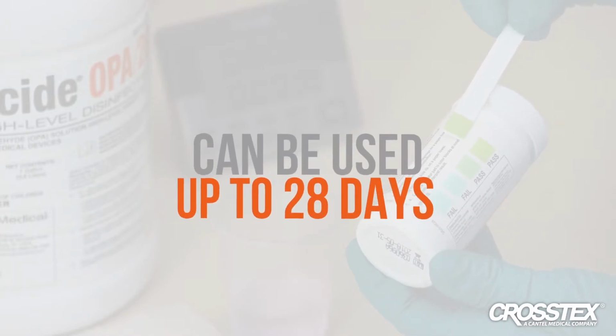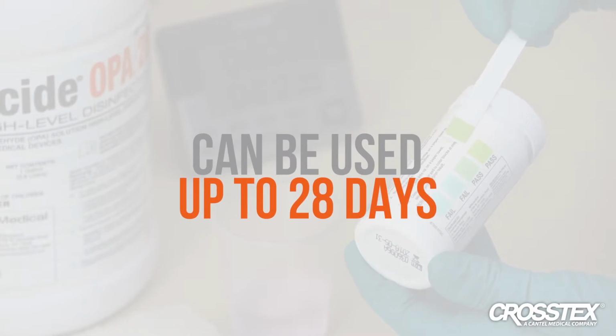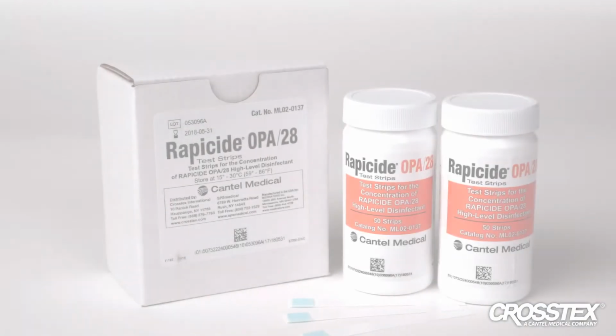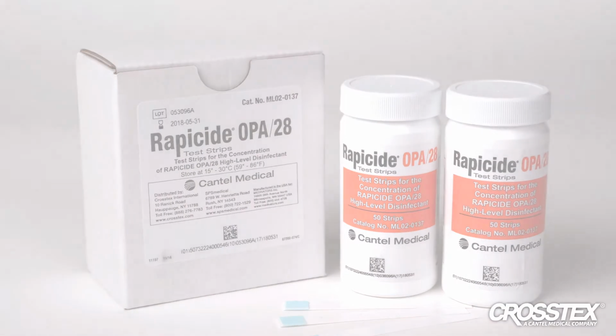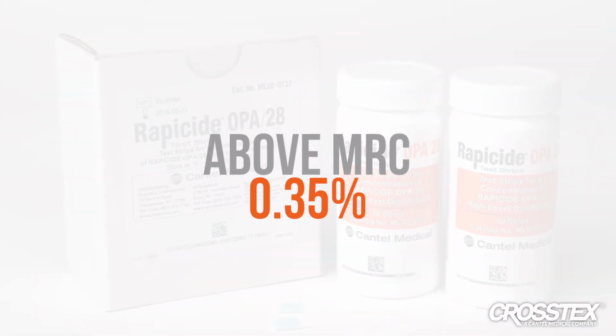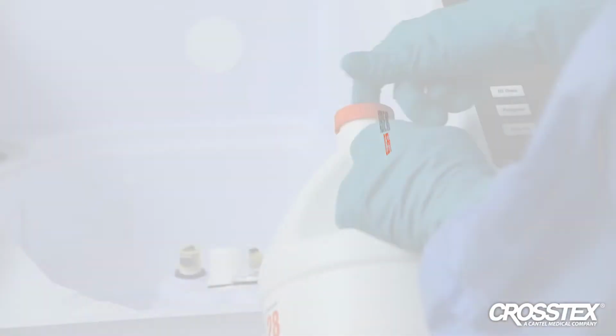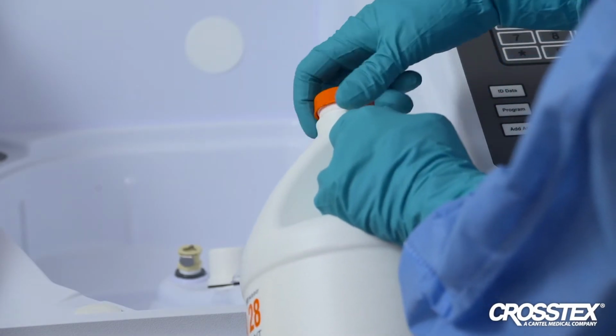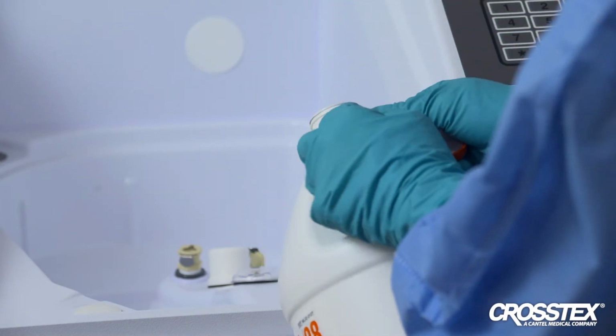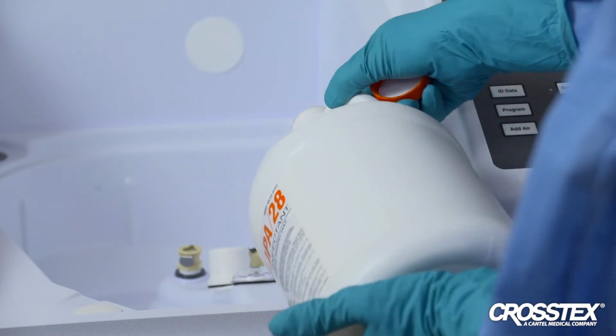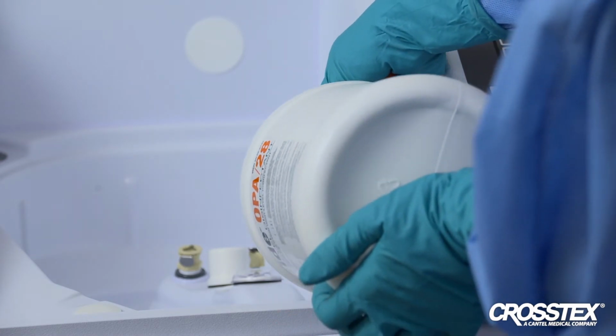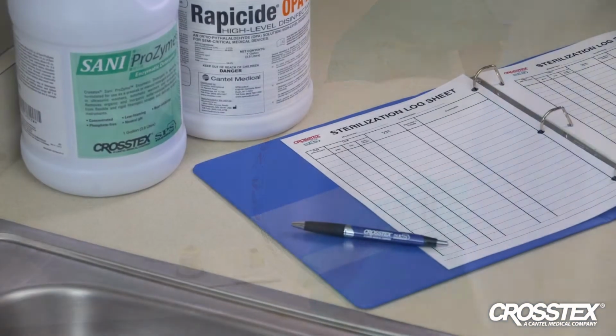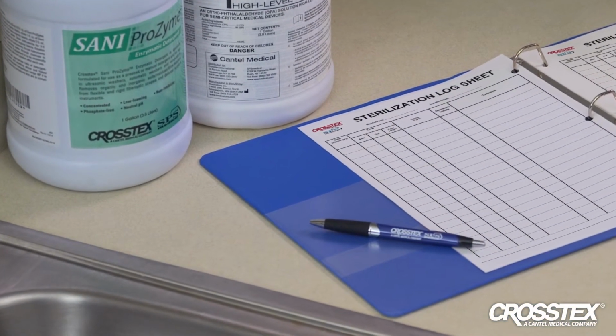The Rapicide OPA 28 HLD solution can be used for a period up to 28 days, provided that prior to each use, the concentration of OPA in the solution is verified using Rapicide OPA 28 test strips to be above the MRC of 0.35%. The solution must be discarded after 28 days. After MRC testing is complete, fill the AER with the Rapicide OPA 28 HLD solution. Be sure to refer to the daily preventive maintenance check sheet for day-to-day preventive maintenance.